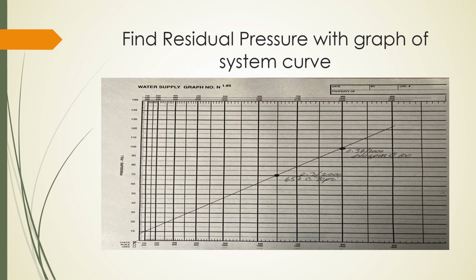So the K does vary slightly with pressure, but for the sake of this discussion and the way people handle this situation, they ignore the slight discrepancies in K factor when using this extrapolating method, and they use it to the square root.